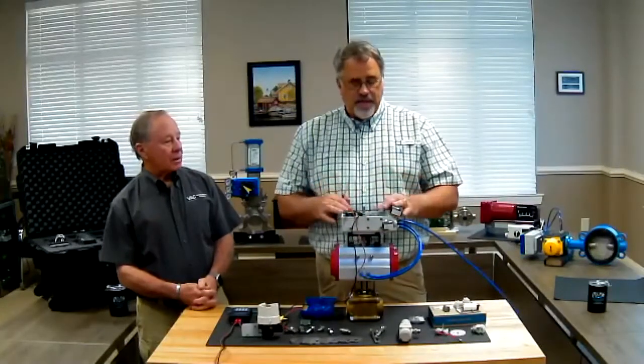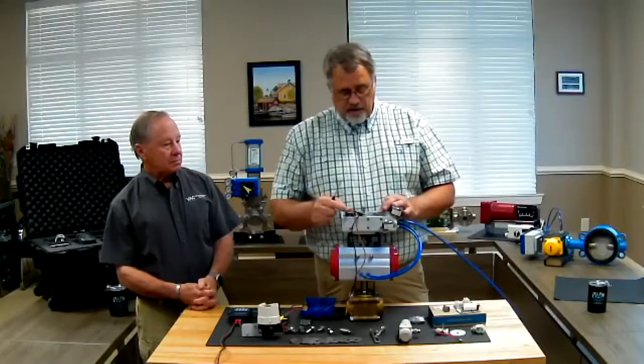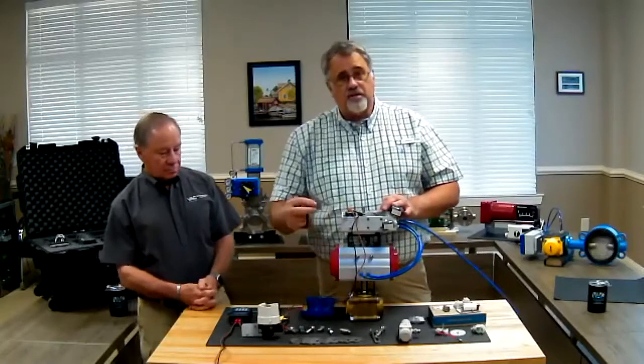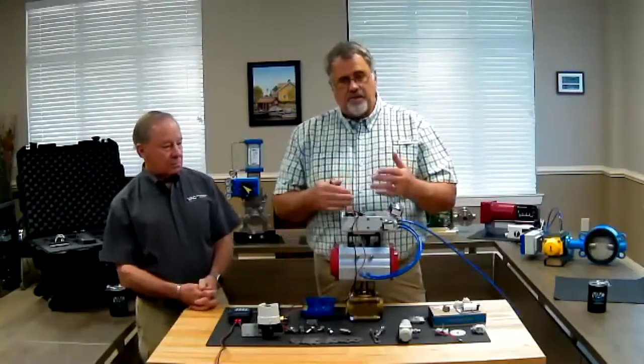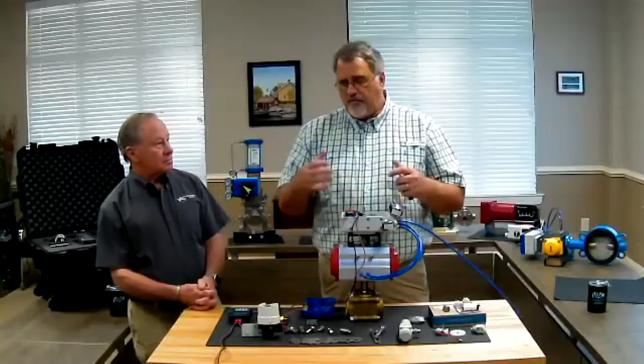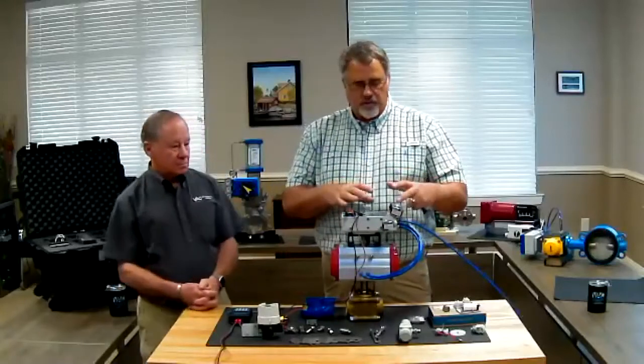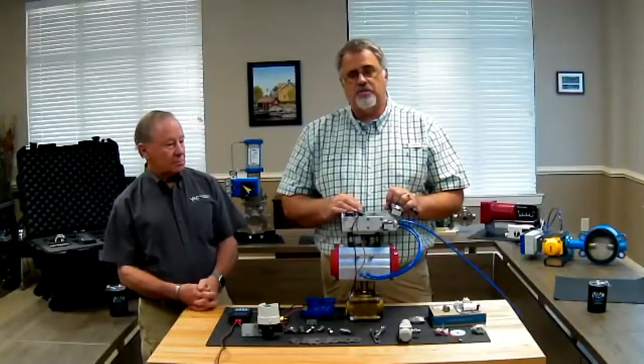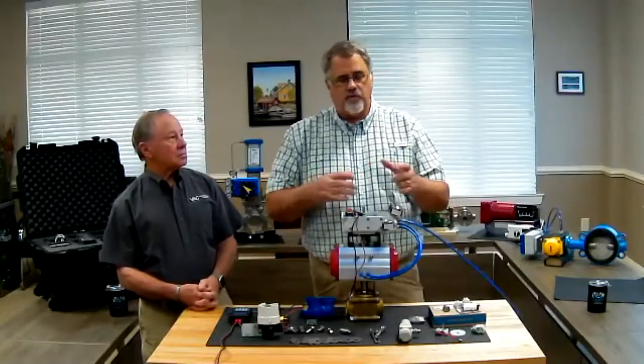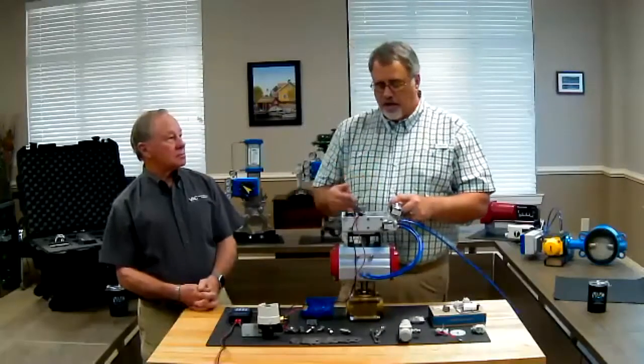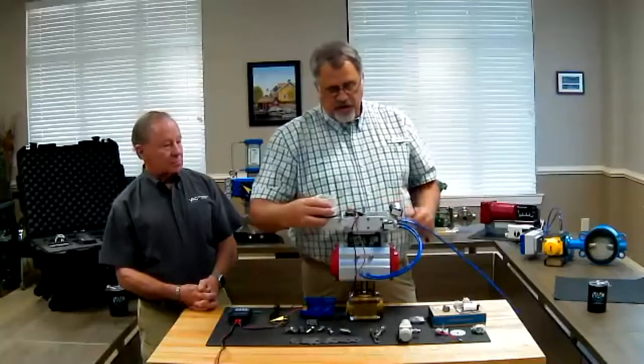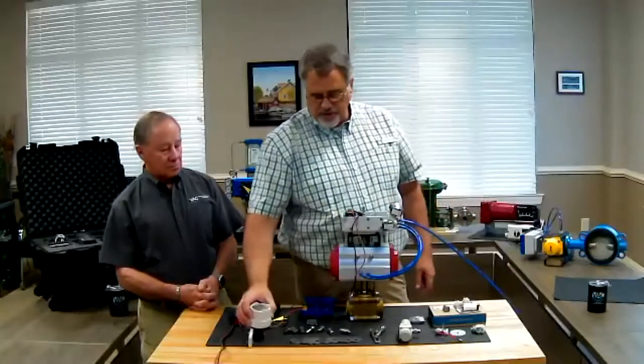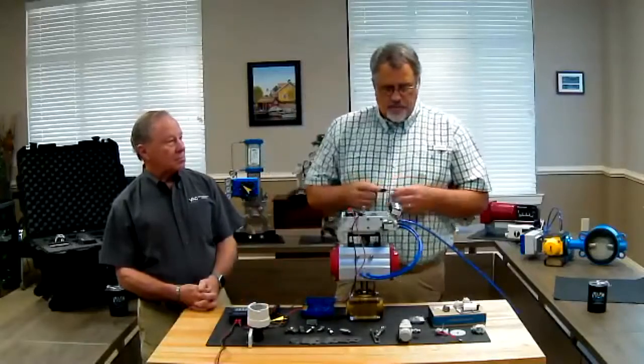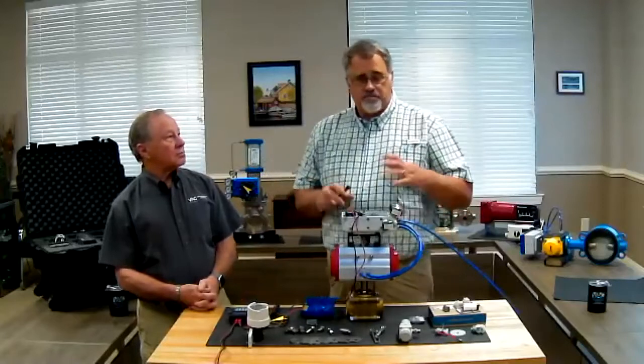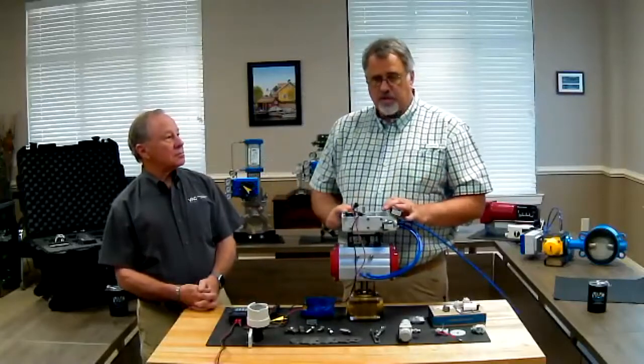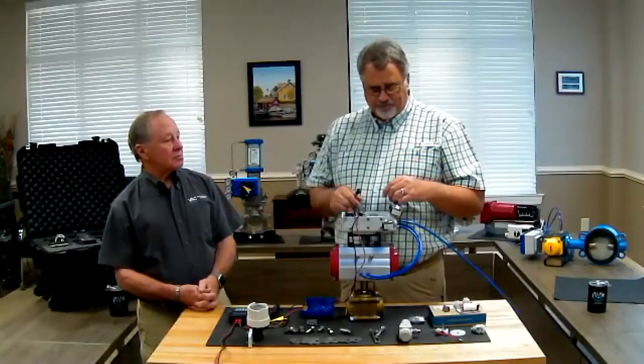So that's basic calibration. I talked a little about replacing the I2P with a pneumatic plate to convert it to a P2P. These are very modular products. Everything we sell, whether analog or digital positioner, is modular in some way to convert it for different things, adding feedback. In this case, we have an explosion-proof I2P that could be mounted on this positioner in place of the standard NEMA 4X I2P. We have intrinsically safe options, all kinds of things we can discuss in detail if you have questions.